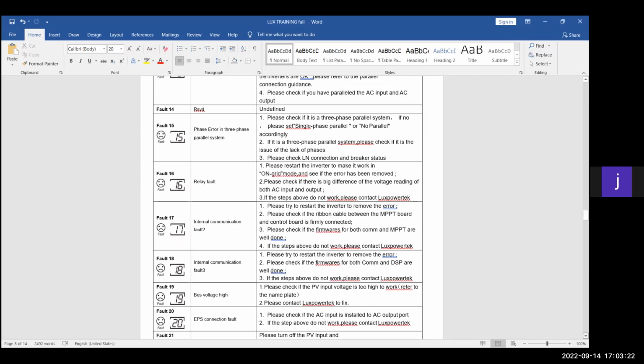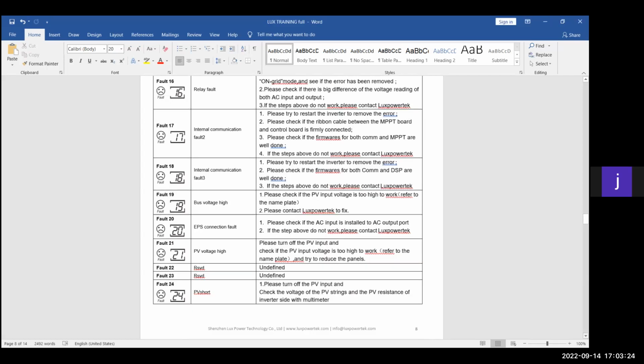Okay, now bus voltage high. We get a lot of these bus voltage high warnings with certain batteries. It's not necessarily your panels that are your problem at that moment. If your panels are, for instance, charging your battery, and your battery stops that charge for that instant at a voltage that's higher than the battery recommends, then the bus voltage of the system goes higher than it should be, and then it gives you a bus voltage high.